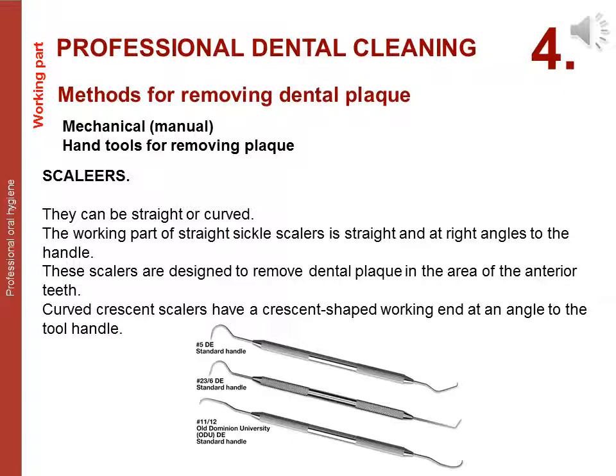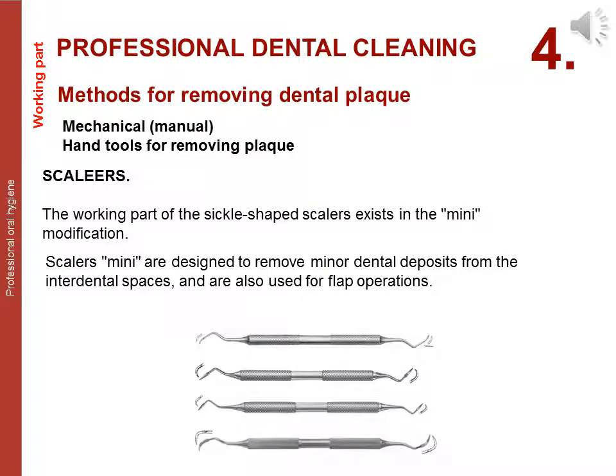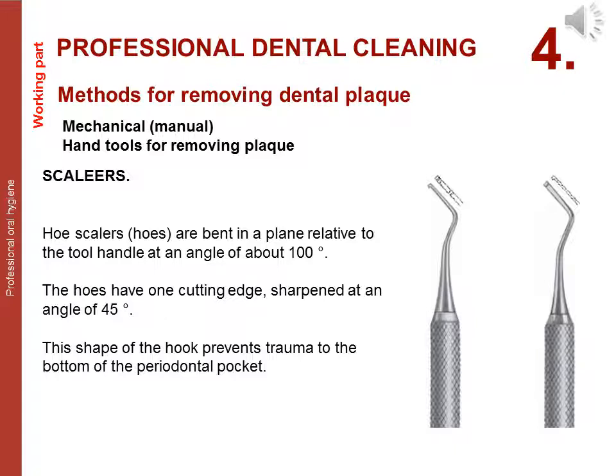Scalers can be straight or curved. The working part of straight scalers is set at right angles to the handle; these scalers are designed to remove dental plaque in the area of anterior teeth. Curved crescent scalers have a crescent-shaped working end at an angle to the handle. Mini modifications of sickle-shaped scalers are designed to remove minor dental deposits from interdental spaces and are also used for flap operations. Hoe scalers are bent in a plane relative to the tool handle at an angle of about 100 degrees and have one cutting edge sharpened at 45 degrees; this shape prevents trauma to the bottom of the periodontal pocket.